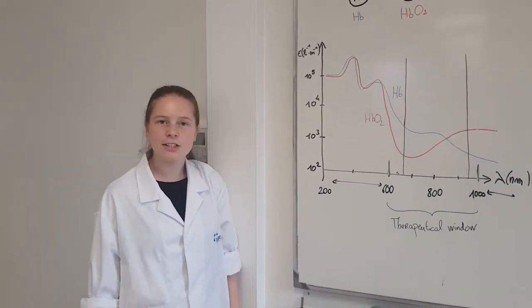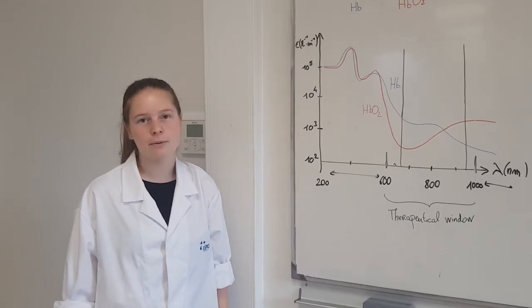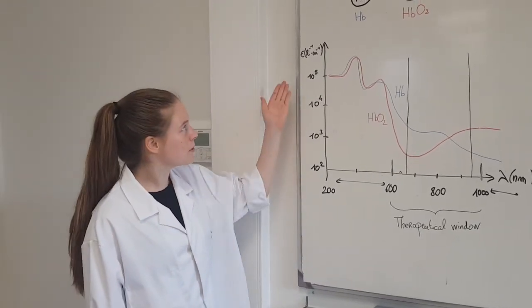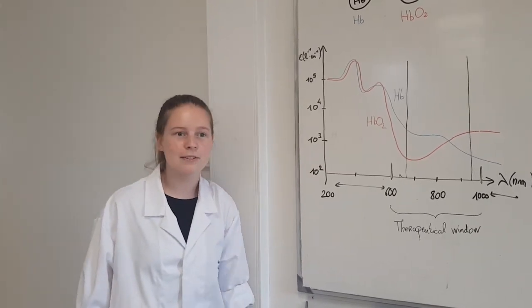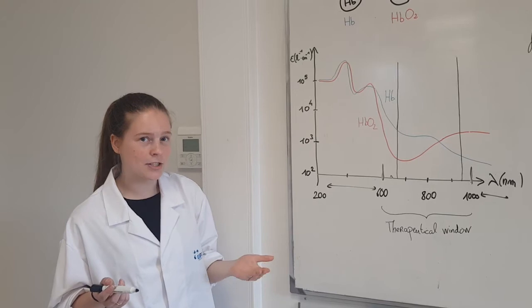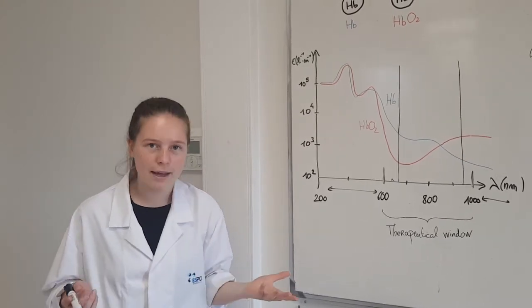Oxygen rate can be calculated from the concentrations of these hemoglobins in the patient's blood. That's why we measured the absorbance of these hemoglobins, which is linked to their concentration in the blood, thanks to the Beer-Lambert law.